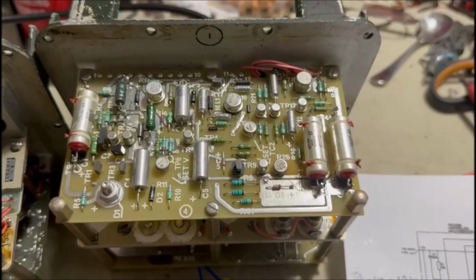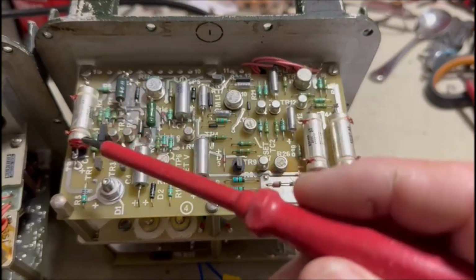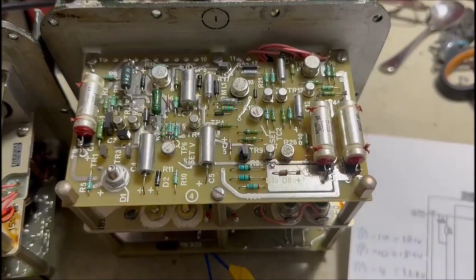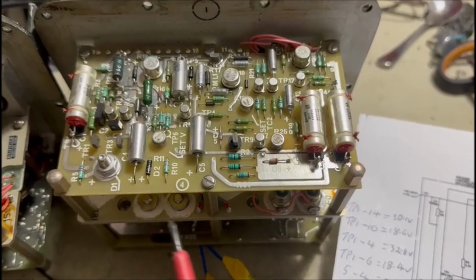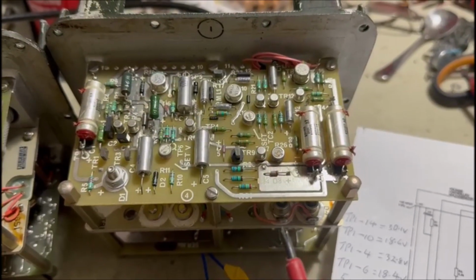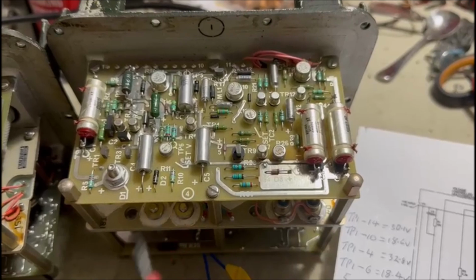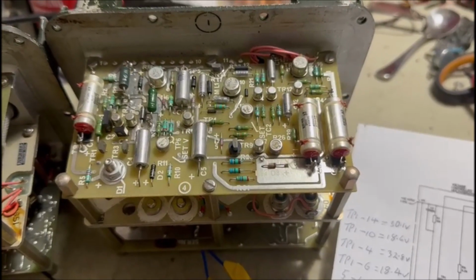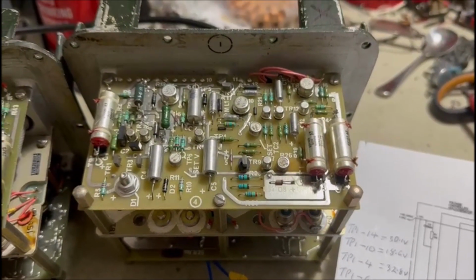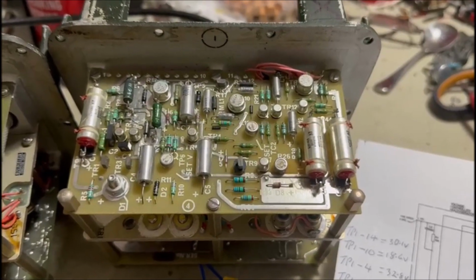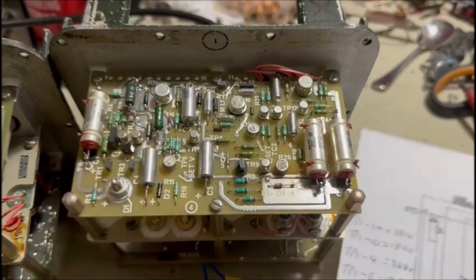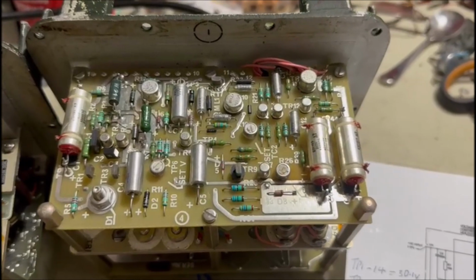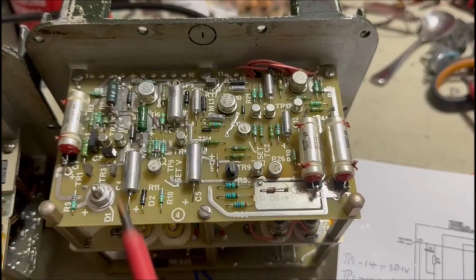So that's the very first thing you should check: do I have voltage here? If you don't, the problems are either associated with some driver transistors, rectifiers, transformers here, or something to do with the pulse generation on the bottom board. In this case, I had my high voltage up here, which was good, so the problem lies on this particular board.